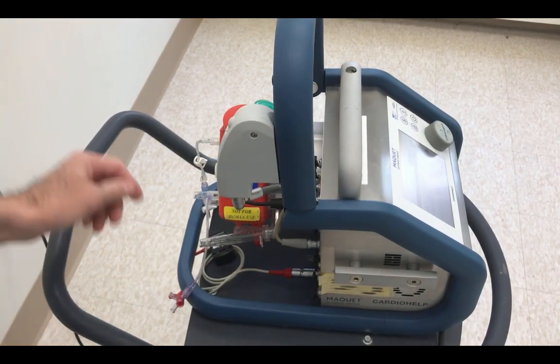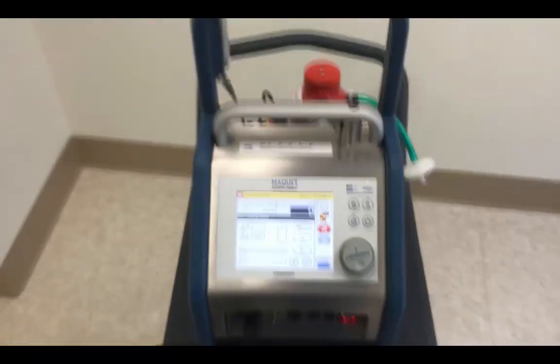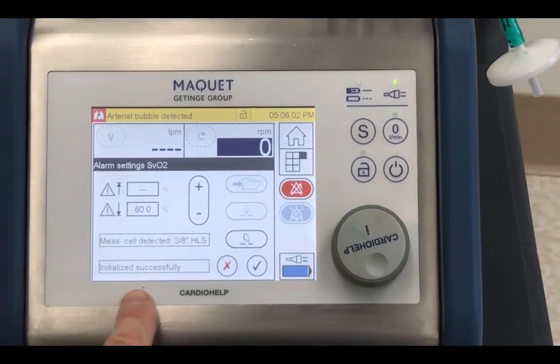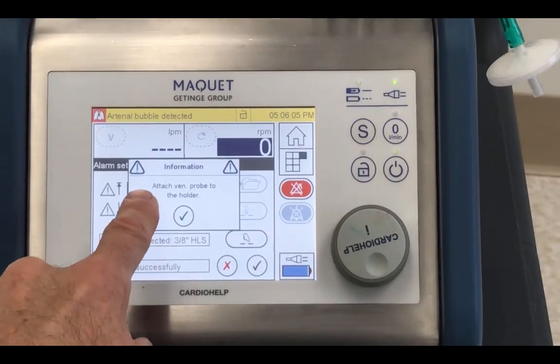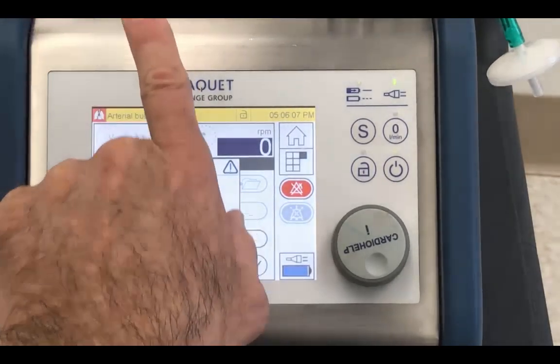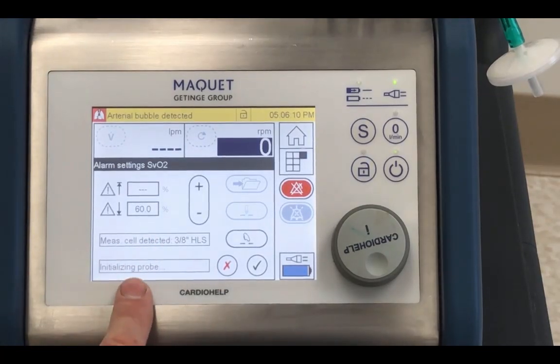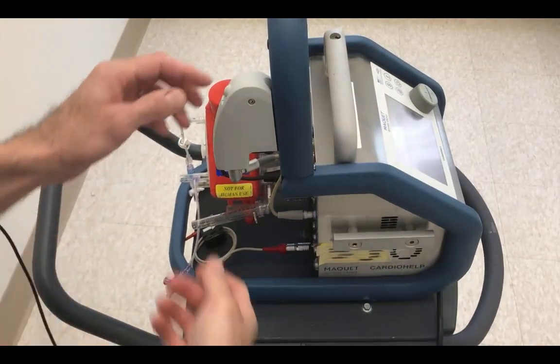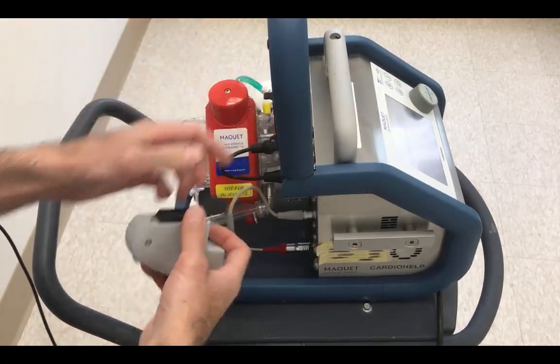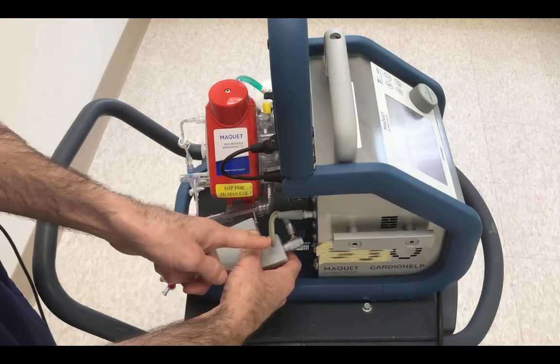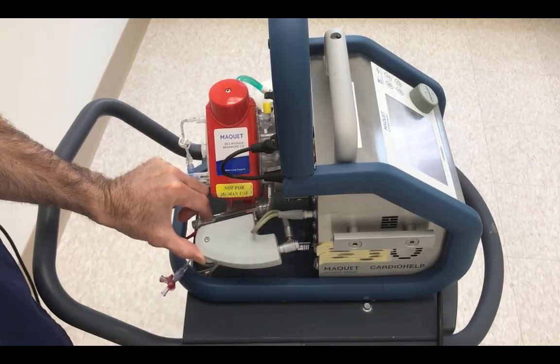Close that up. And you could come around and then tell it to initialize. And it's telling you to attach the venous probe to the holder, which we just did, and wait for it to say that it's done. Once it has initialized successfully, disengage it from the calibration bracket and place it back on in its clinical position and drop the door.